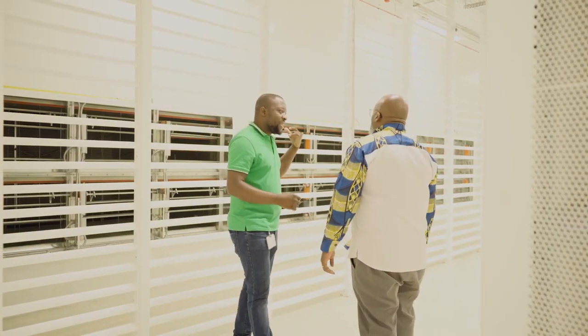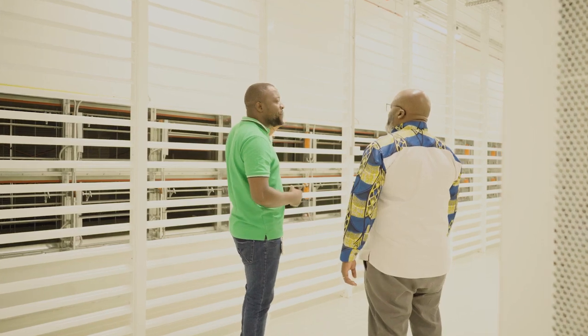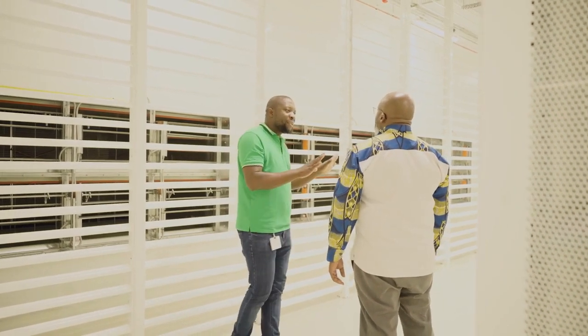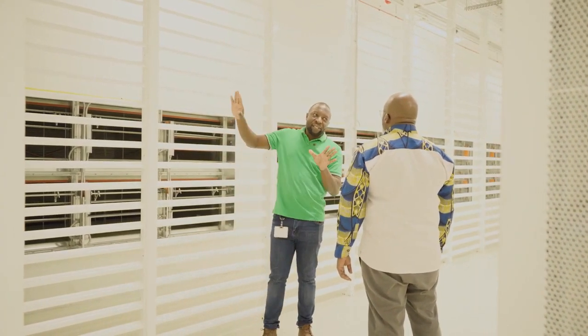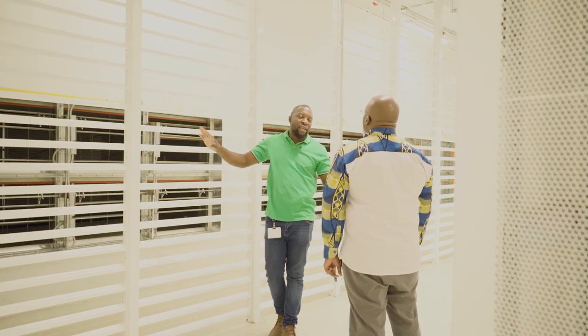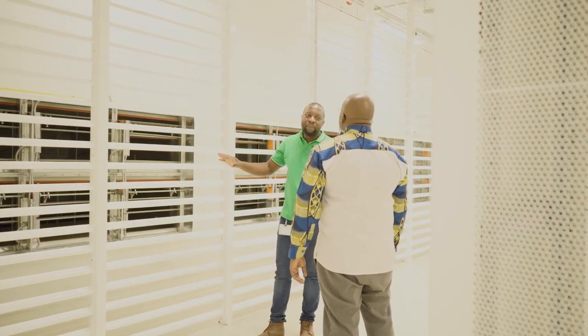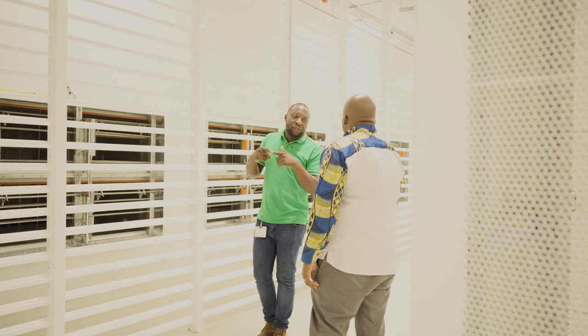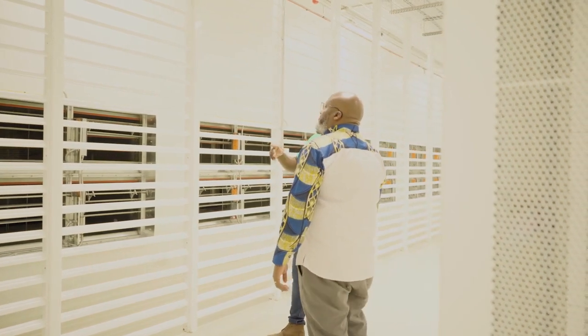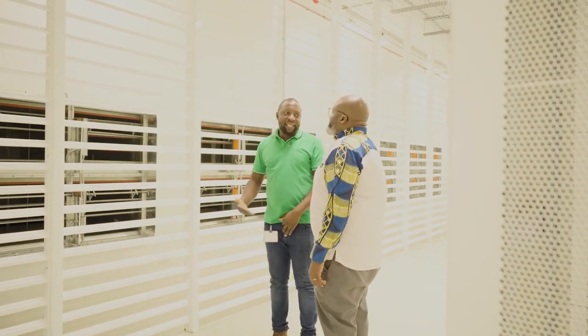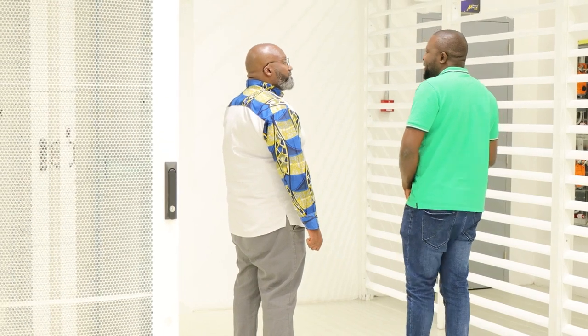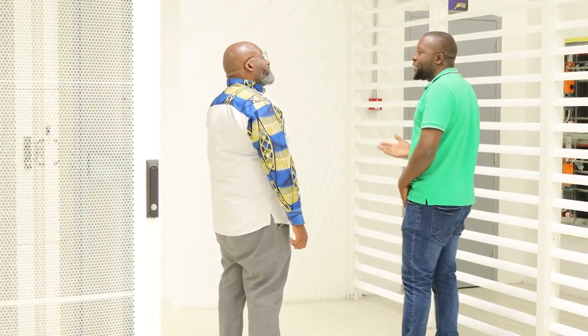Free cooling is where we cool this data hall using the ambient air temperature. We just get the outside air and use it to cool the air inside the data hall, and it's an air-to-air technology. That doesn't mean we bring outside air directly into the data hall, because it has impurities we cannot afford to bring in.